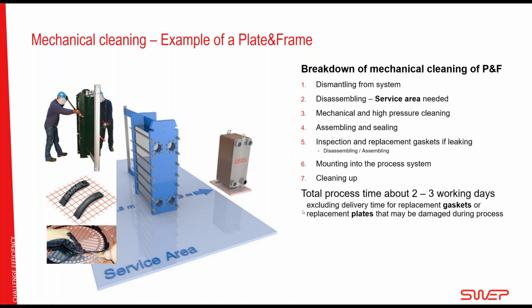Make sure that you have the service area available. We clean it with mechanical and high pressure cleaning. We assemble and seal it again. Test it that it's working. If it's leaking, we might have to open it again and maybe change a plate or a gasket that were damaged. And if we open it, maybe we should change all the gaskets anyway, which would add some extra time.